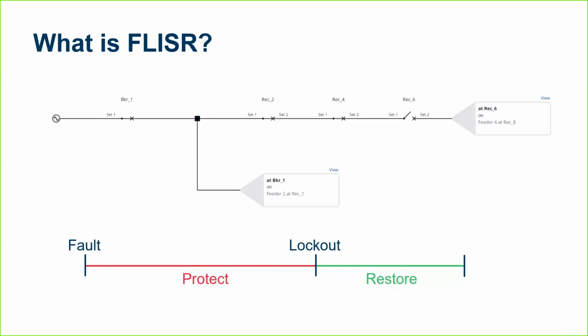A reclosing device is an incredible reliability improvement to the distribution system. So if a fault occurs here on this system, a breaker or recloser should trip and immediately reclose. Depending on the circuit or the utility or the time of year, the number of times that device attempts to reclose may be once, twice, 3 times. Eventually, though, if that fault just is there every time we re-energize the line, the recloser gives up. Right? It reaches its shot count. It goes into what's called lockout. Lockout, we can monitor remotely, and we can see when lockout is asserted that recloser is open and is no longer going to attempt to reclose on its own. That fault is now an outage. It is permanent, a permanent outage.